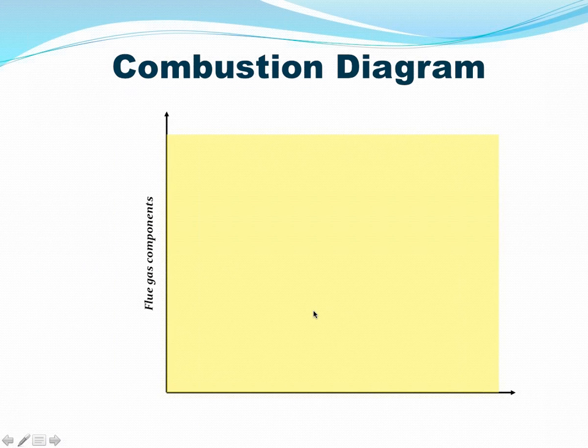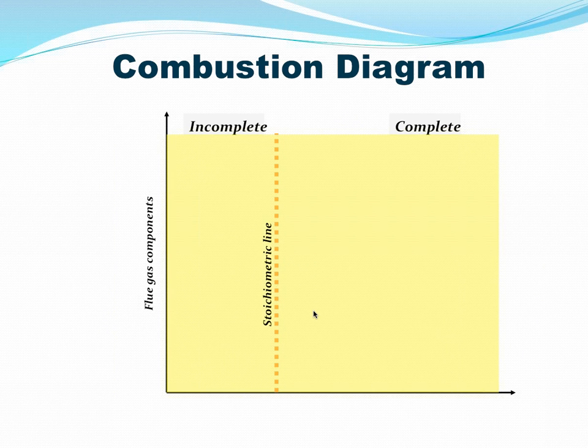Okay, getting back, we'll get into this combustion diagram and try to develop the concept of CO air-free. This is part of our combustion seminar, which is coming up if you want to hear a more lengthy explanation of the whole combustion process. The stoichiometric line is basically the balance point of combustion, where the chemical equation balances, where you have just the right amounts of fuel and oxygen to get perfect combustion and the perfect byproducts of combustion. So on either side, you have either incomplete combustion, with not enough air for the fuel available, or complete combustion. So we have either excess fuel or excess air. In some ways, this mirrors the concept of reaching the lower explosive limit and upper explosive limit. There's that notion still in here, with the quantity of air or oxygen available changing.